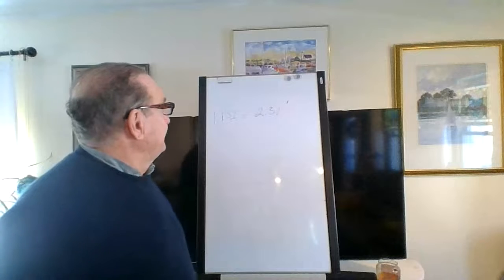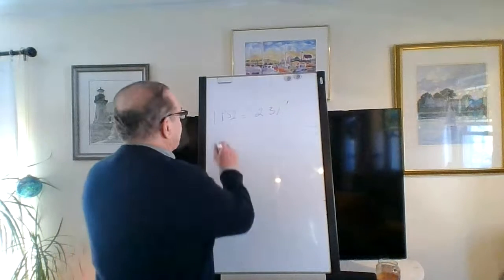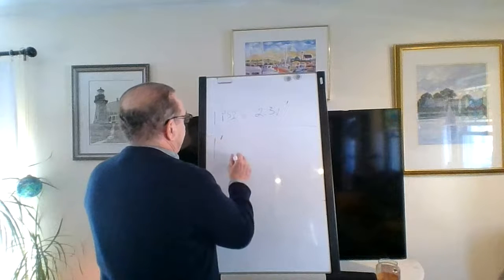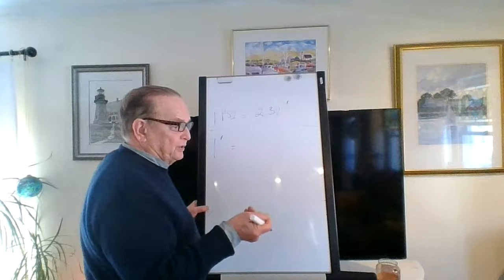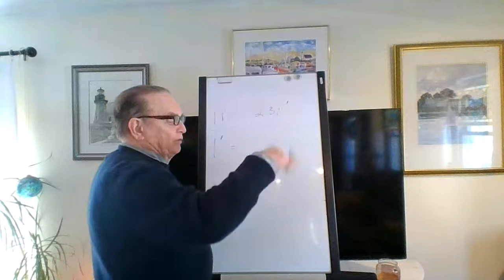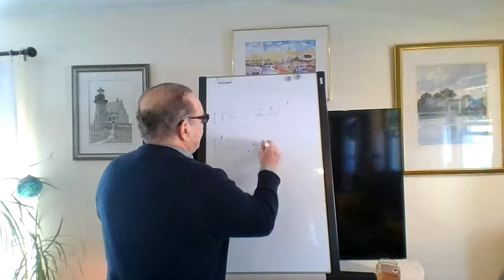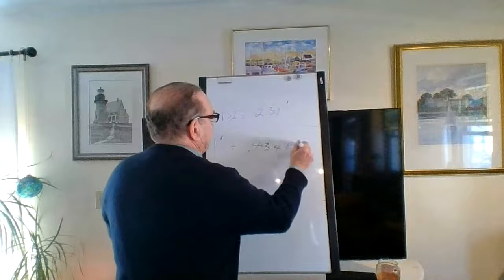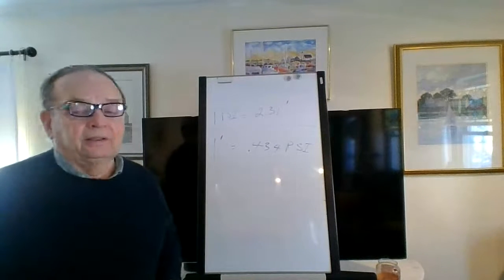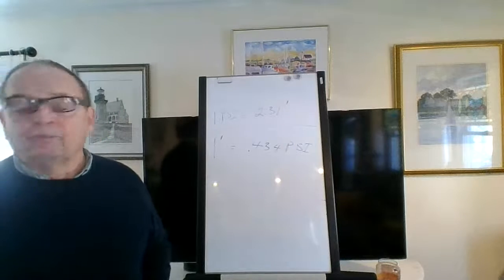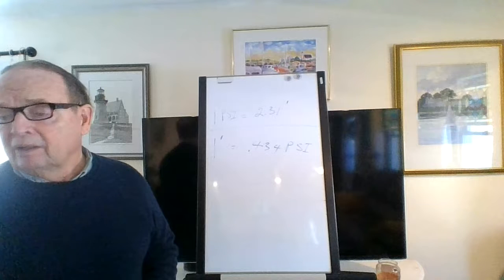Okay? Now, the flip side of that would be how much pressure in 1 foot, right, of anything, pounds per square inch at the bottom. So you got a gauge stuck in, and you have a leg of water a foot high. Okay, a foot only produces 0.434 psi. Okay, these two little formulas here will give you the answer for most of what you need from this chapter in our code.